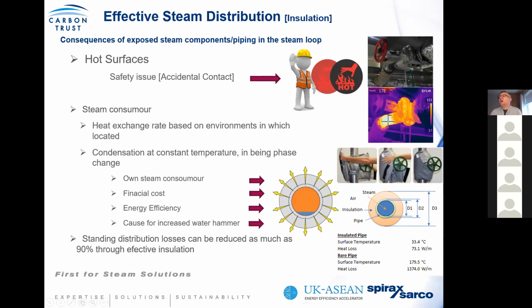So what you could also find is that valves like these increase the cause for water hammer, because as you radiate heat, the steam inside condenses, creating water, and where it's not removed effectively, you increase the likelihood of water hammer damage. You could easily apply what we call removable insulation jackets, and in doing so, you can eliminate as much as 90% of the standing losses.